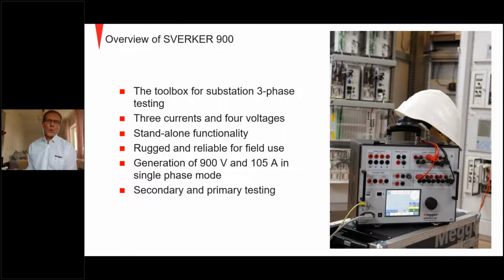So, a short overview of Sverker 900. It's a toolbox for the substation, for doing three-phase testing. It has three currents and four voltages. It's standalone, rugged and reliable for field use. You can generate up to 900 volts in voltage and up to 105 amps in current when you have the Sverker connected in single phase mode. It could be used for doing primary injection in this case.